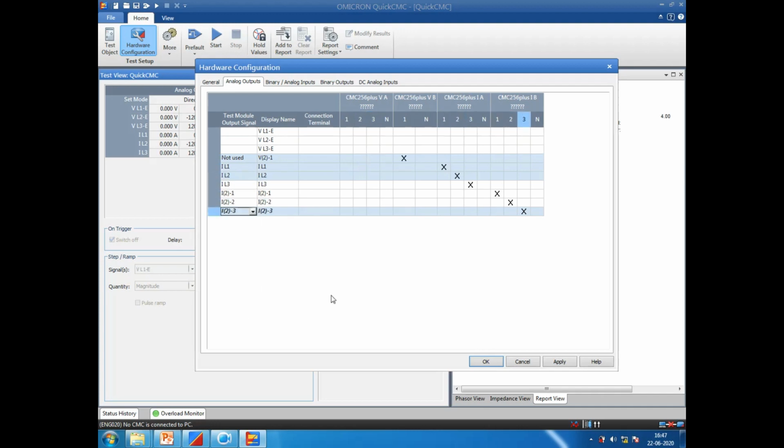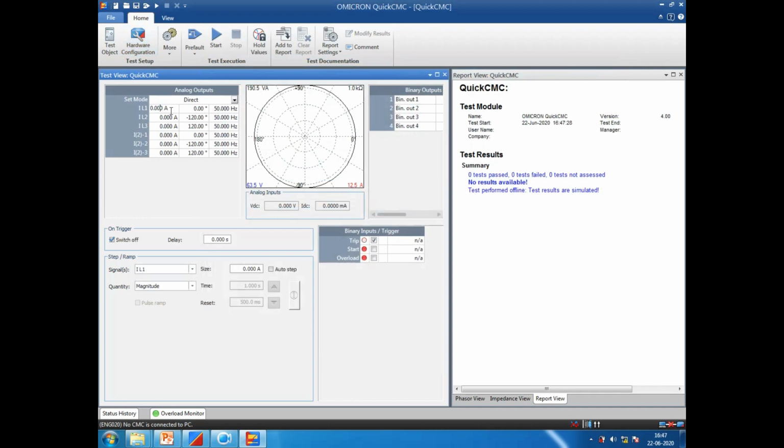I inject current for incomer 1 as 0.66 and outgoing 1 as 2 amps on the secondary side, and I make the angle 0 with balancing for incomer and opposite angle for outgoing. This 0.66 and this outgoing 2, if you see it on the secondary side, looks like an unbalance actually, but for this only I have shown the matching factor previously.